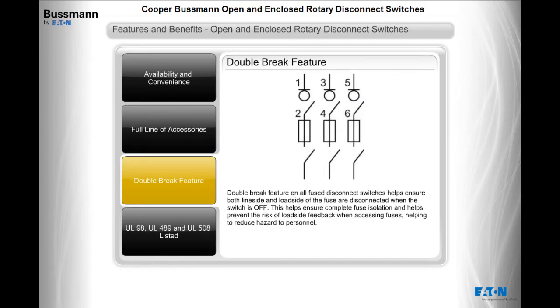The double break feature on all fused disconnect switches helps ensure both the line side and load side of the fuse are disconnected when the switch is off. This helps ensure complete fuse isolation and helps prevent the risk of load side feedback when accessing fuses, helping to reduce hazard to personnel.